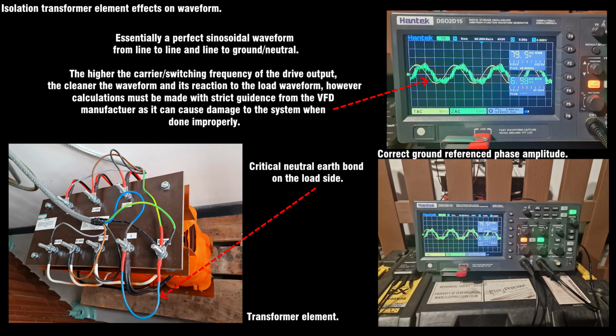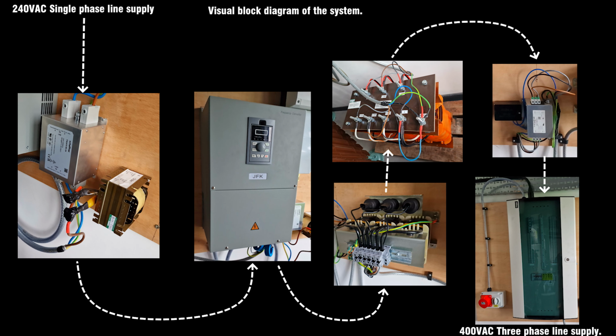This is where the isolating transformer comes into play. Not only can it electrically isolate the VFD side, which has its benefits, it can provide you with a neutral and proper ground referenced lines, which are vital for CNC machine tools and sensitive devices. Then from the transformer, that goes into a final RFI filter, then to my distribution board, which has surge and all relevant protections for the machines that I'm using.